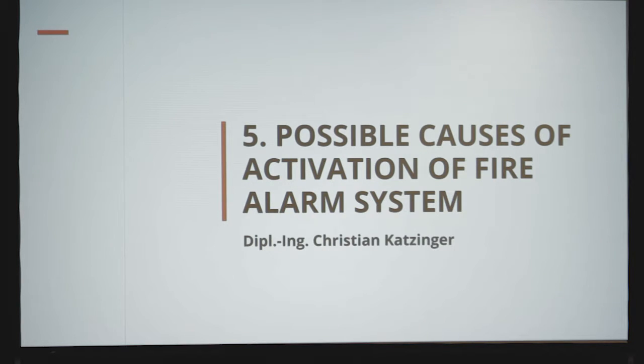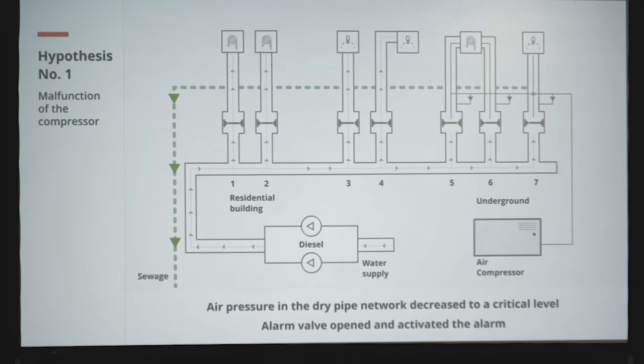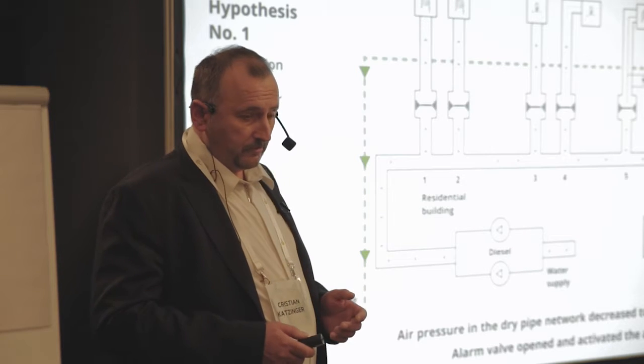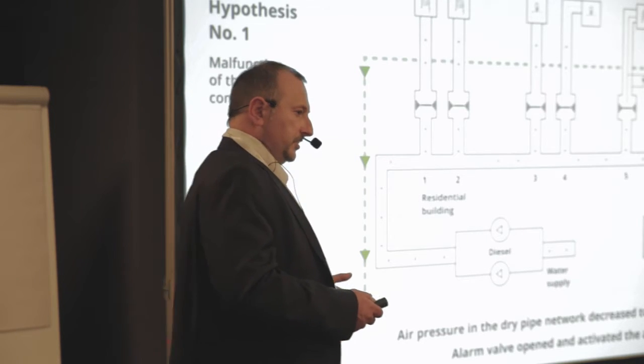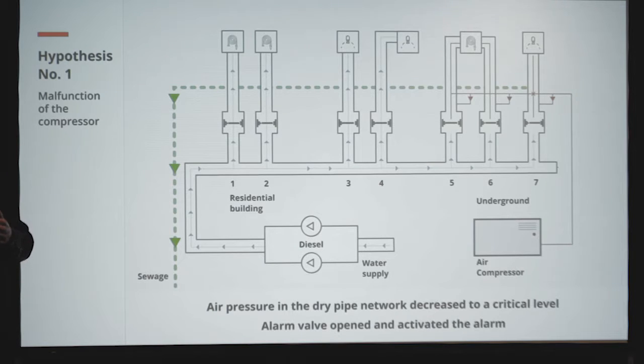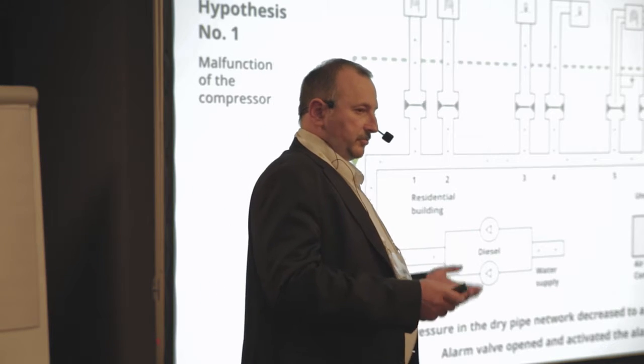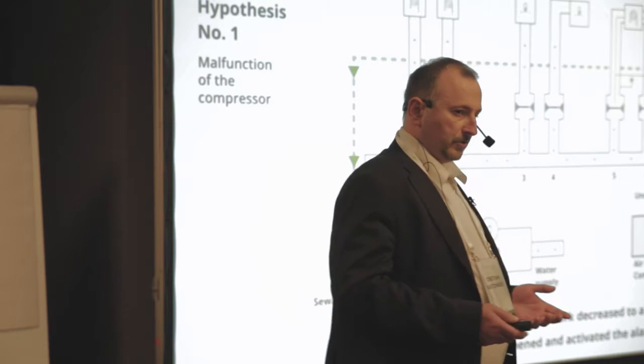So it's interesting to know what is the reason for the activation of the fire alarm system giving a false alarm at this time. As I already told, the fire hoses and the sprinklers in the underground and the pipes in the underground were of dry system. They were filled with compressed air. And one possibility could be that there is a small leakage inside a pipe system of the fire hoses. So the air pressure is dropping, and when the pressure is low enough, then a valve would open.